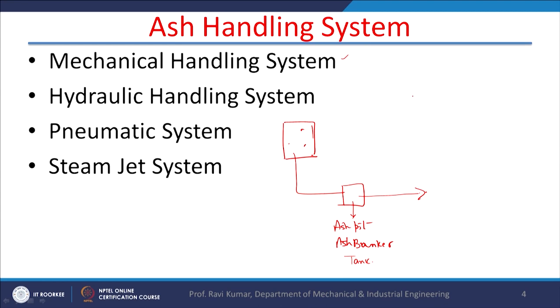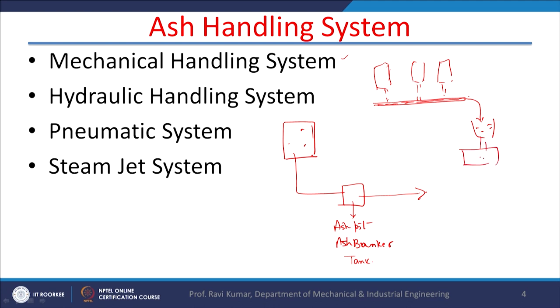In mechanical systems, there is a conveyor belt. Ash comes from combustion chambers and falls onto the belt. There is a water trough — a narrow lane where water flows — and the water and ash make a slurry. This slurry is transported to the ash bunker and from the bunker it is sent by truck to somewhere else. This is the mechanical handling system where a conveyor belt and water trough are used to create slurry which is then transported.